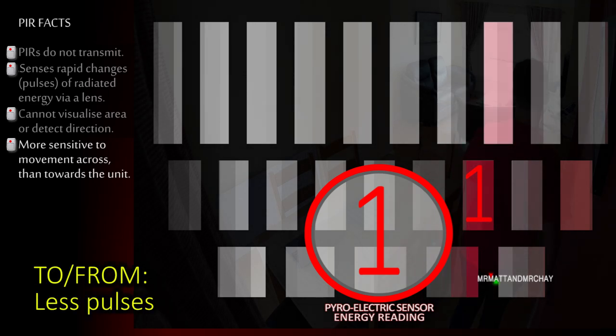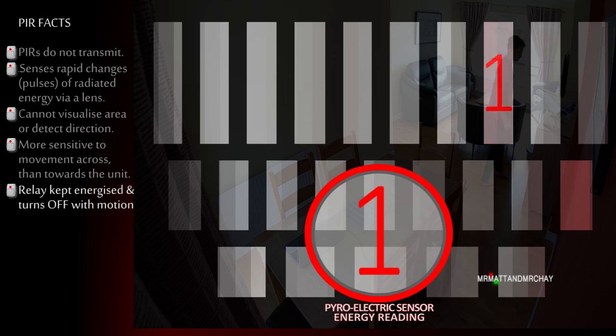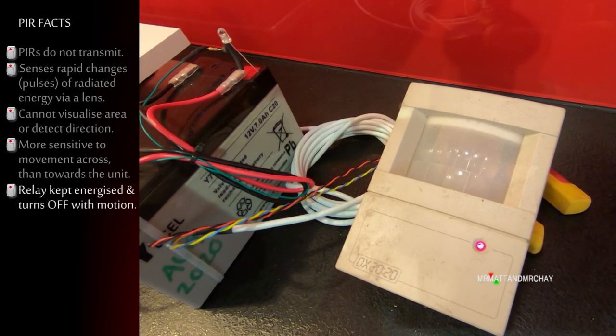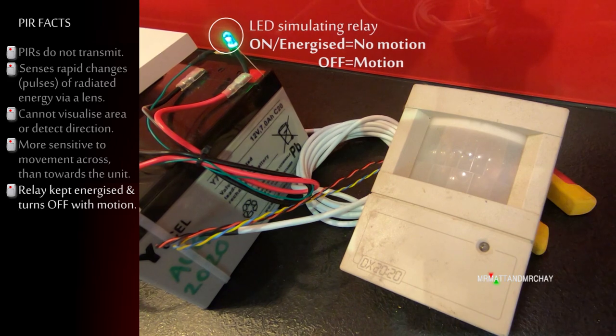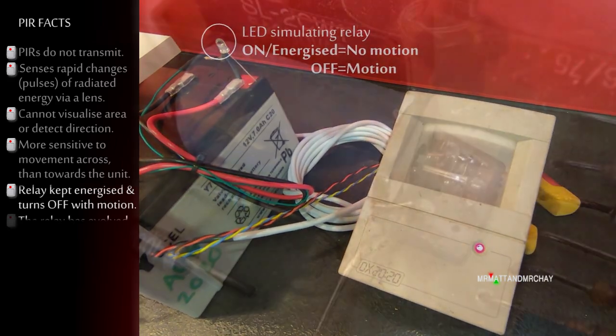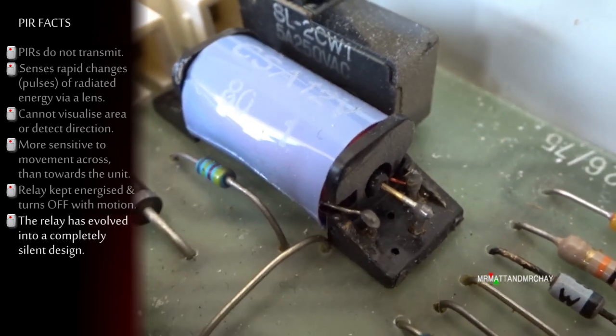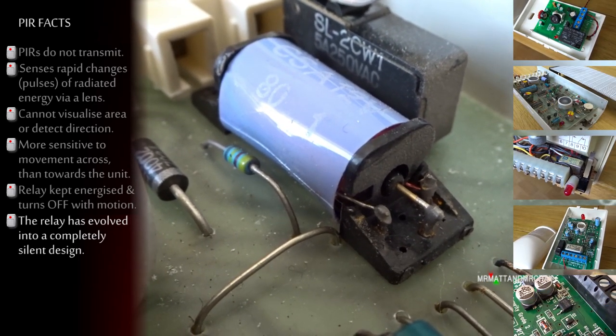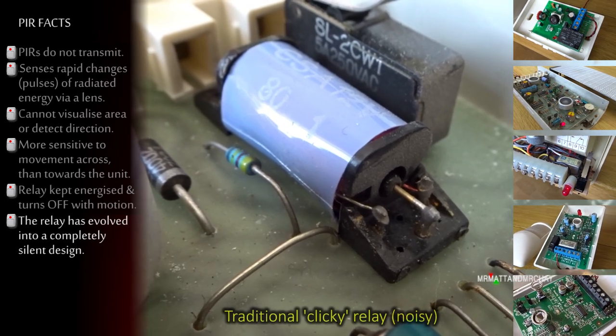The output relay is kept energized until motion is detected. A power loss or disconnection of power results in a continuous alarm output. Over the years, the clicky relay that signals motion to the control panel has evolved into a completely silent design.